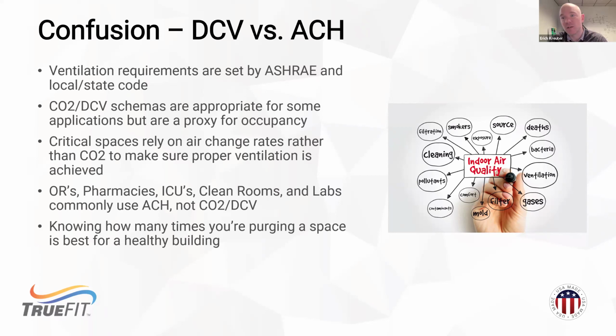We get some confusion as, I'm already doing demand controlled ventilation. Why do I need to measure air changes per hour? And I'll say here that DCV is not necessarily ventilation. We're standing in a CO2 measurement for occupancy, but a lot of the new standards are wanting guaranteed airflow rates per occupant that is actually in the space, not a design load, and really driving those efficiency standards more in real time. So there's a reason why we don't see CO2 sensors in ORs and hospitals and pharmacies and things like that, because again, ASHRAE has decided that as an industry, we need to do air changes per hour to make sure that ventilation rate is proper versus a stand-in measurement such as CO2 or PM.